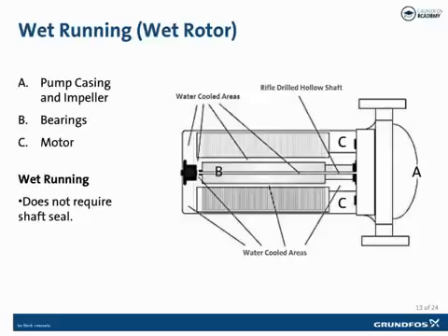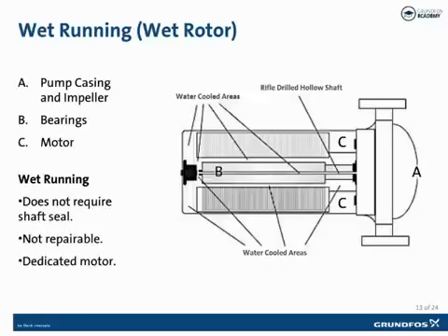Since the wet rotor pump is a one-piece pump, repair is not practical. The motor is dedicated and designed for a particular casing, so a motor exchange is not possible. One-piece pumps are usually less expensive than three-piece pumps, and if a failure occurs, the pump is usually replaced rather than repaired. One-piece pumps are now also available with integrated variable speed drives and sensors, making them very application-flexible and cost-effective when considering operating costs.